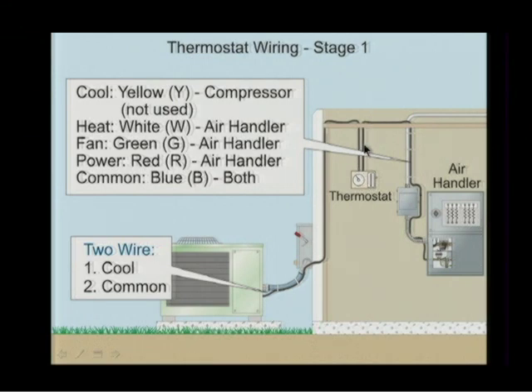If you take the red wire, which is your power, and you touch the green wire, the blower should blow. You'll hear it turn on. If you take the red wire and you touch the compressor, of course, assuming power's on there, you'll hear the compressor kick in. You take the red wire and you touch the white terminal of the thermostat, then you're going to be smelling the heater elements heating up without the ability to cool them down because we're not moving any fan.